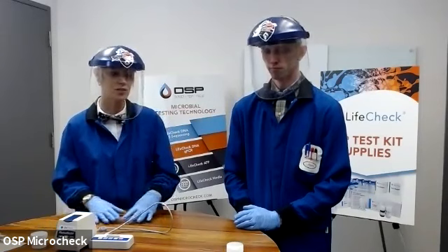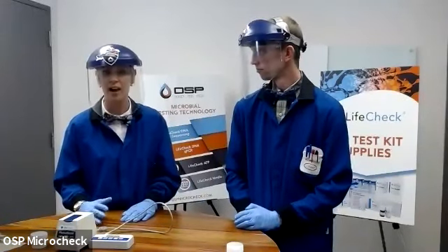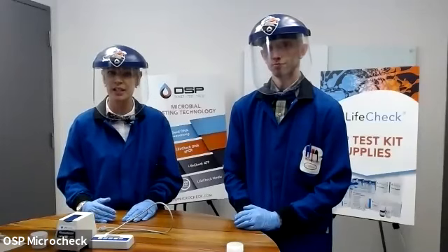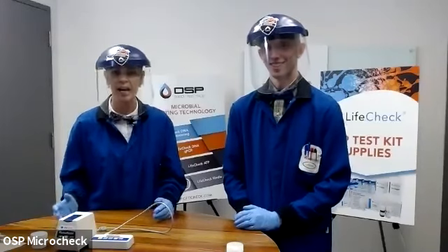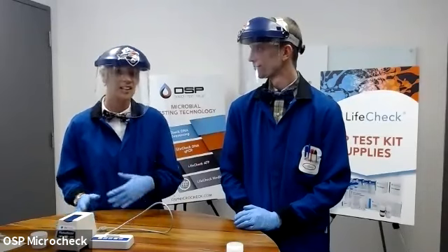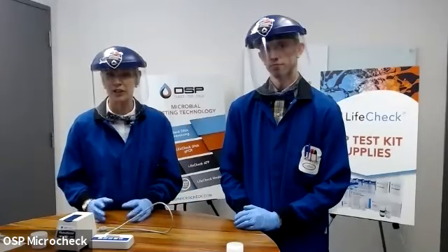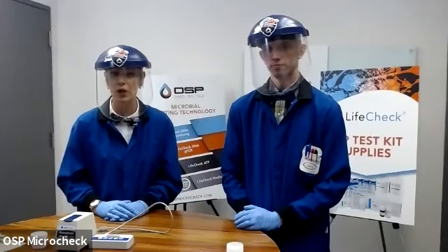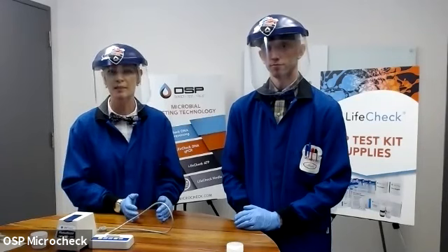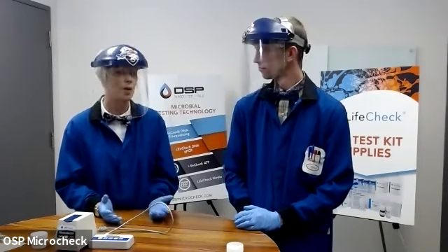So again, if you start there, there may be some systems that are really harsh, high temperatures, not a lot of nutrients. You can actually have a really high amount of microbes and it not correlate to any direct issues in your system. On the other side, you may have a facility that is full of nutrients, a great temperature for microbial growth, and you may have to move those limits down lower because even a low amount of microbes could easily flourish and become an issue.